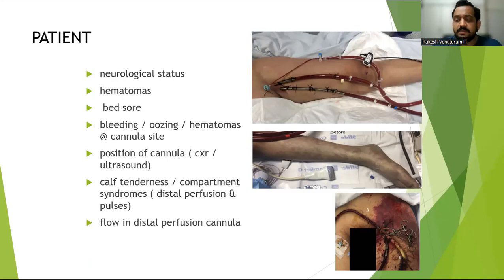And then the flow in the distal perfusion cannula. In patients on VA ECMO, this is the problem which we face. So what we generally do is keep a Y connector here, and from the Y connector you have a 3/8 tubing, and from 3/8 there is a step down to a 1/4 connector and 1/4 to a distal perfusion connector. So if you are doing this type of arrangement, and if you have a Centrimag machine, you can keep the flow sensor here and you can see the distal perfusion flow here.